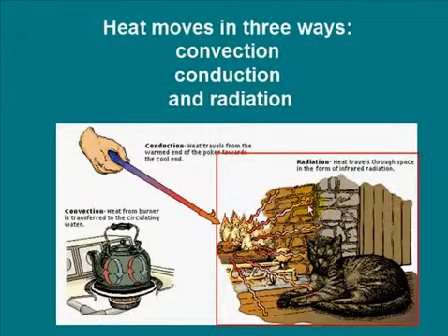All right, that's radiation. If you've walked through a warehouse with radiant heaters, it can be 40 or 50 degrees in the warehouse, but walk up to a box or a table and put your hand on it, if they're using radiant heat, that object is warm. And that's how radiant heat works. It heats up the object just like the sun heats up the earth, and then that heat radiates back out to space again, which is cold, because hot always goes to cold, and on the way out it warms up the air. The same with radiant heat in a warehouse. Heat up the objects, they radiate heat to the air and temper the air.